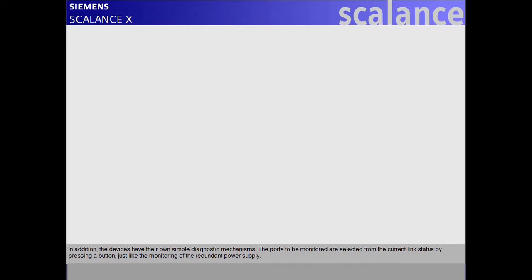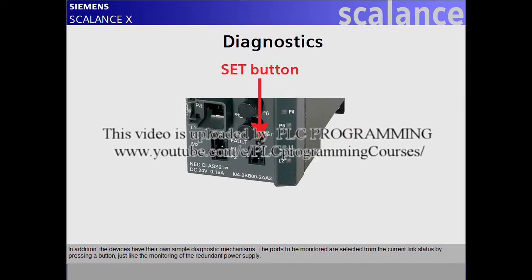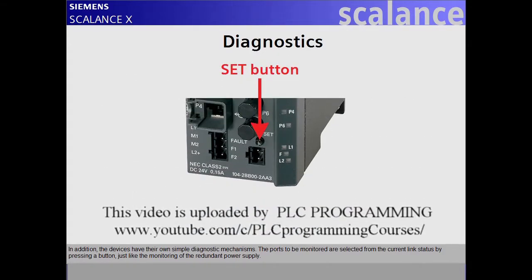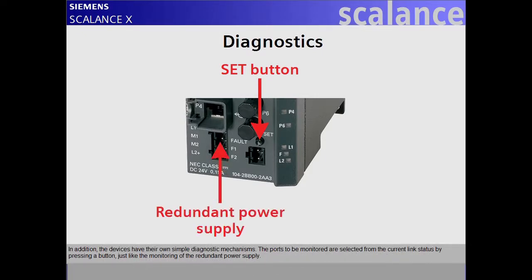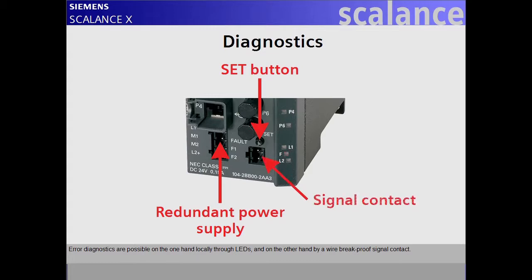In addition, the devices have their own simple diagnostic mechanisms. The ports to be monitored are selected from the current link status by pressing a button, just like the monitoring of the redundant power supply. Error diagnostics are possible locally through LEDs and on the other hand by a wire break-proof signal contact.